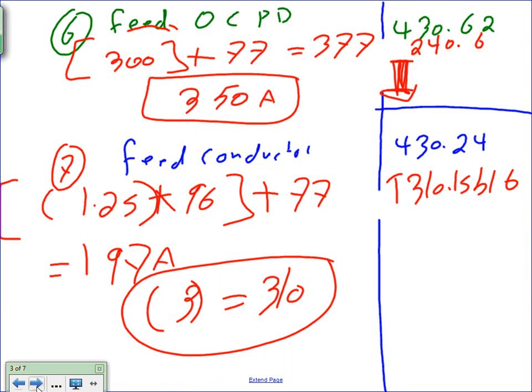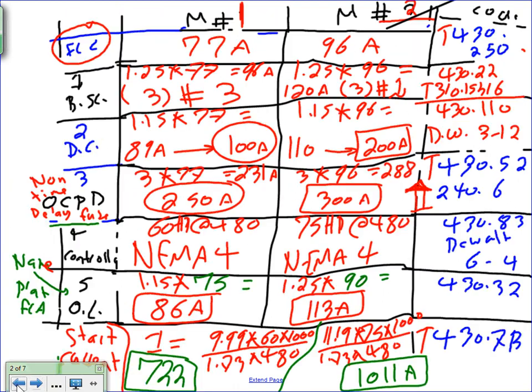Number 6 is the feeder, and number 7 is, because start current is not something that we really size. We don't size it, but we have to be aware of it when we set the circuit breaker, or when we do coordination and so forth. So it comes in handy. Very good question. Why would they worry about start current? That's what Chris is asking me. Start current, guys, comes in very handy when I look at the overcurrent device coordination later on. Just FYI.